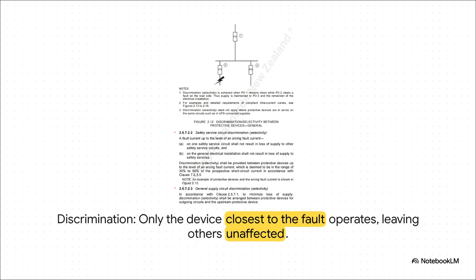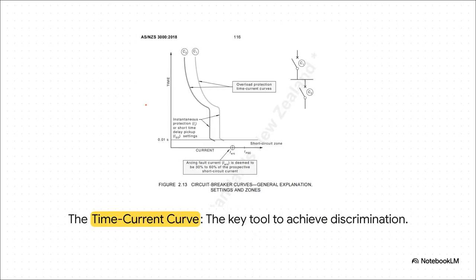That is the whole point of discrimination. You isolate the problem to the smallest possible area and cause the least amount of disruption. So how do we actually make that happen? Well, the main tool in our toolbox is this, the time current curve. Think of this graph as the device's unique fingerprint. It tells you exactly how long it'll take to trip at any given current.